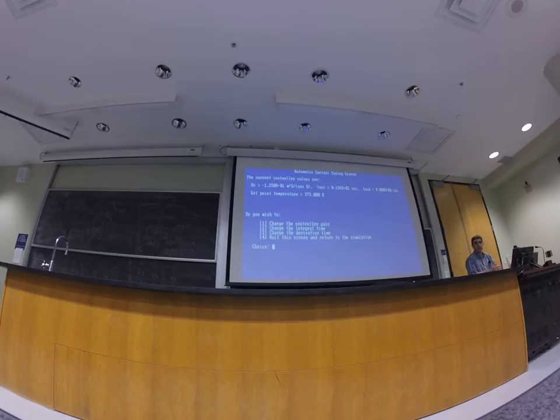So how do I eliminate integral action? If I do just proportional control, I shouldn't have the integral. 0, 0. But I can't do that. I have to put a tau I. So how do I eliminate the 1 over tau I integral? Very big. Make tau I very big. So I will change the integral time constant to something really big. How about 1 million?